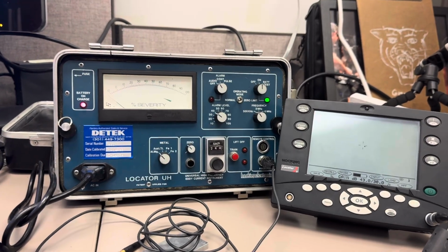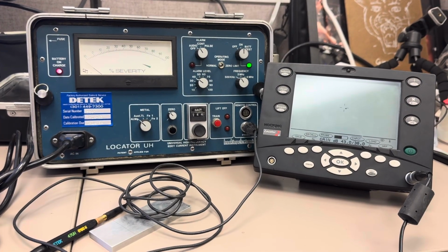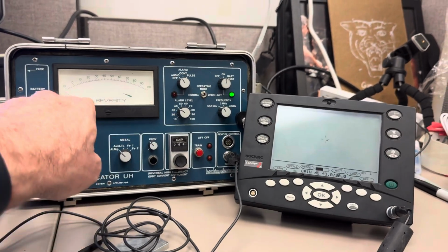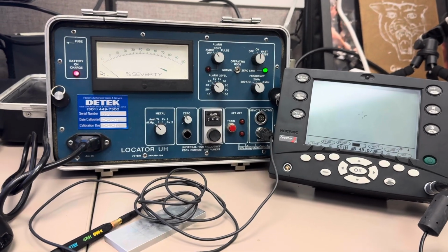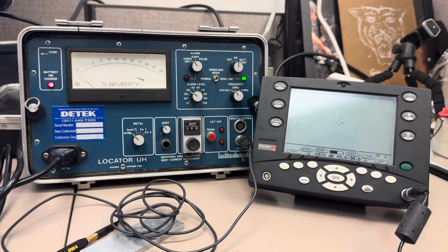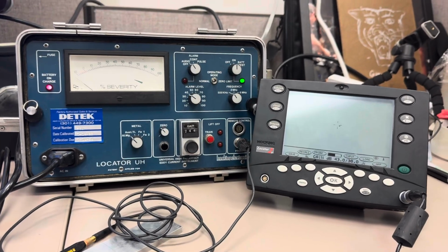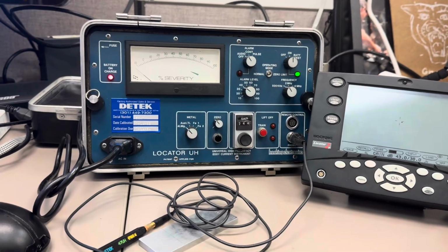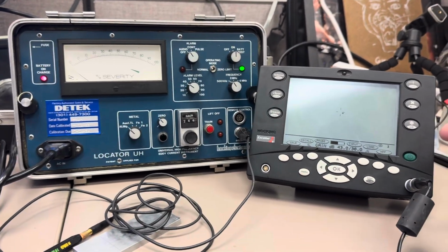A calibrated display is one that is calibrated for a specific type of measurement. For example, if you had a conductivity meter that had percent IACS listed on the meter, that would be a calibrated display for measuring conductivity and IACS. However, it's likely that all your instrument is capable of testing is conductivity and IACS. Same way, if you had a meter that had resistivity in microohm centimeters, that would be a calibrated display to measure resistivity.